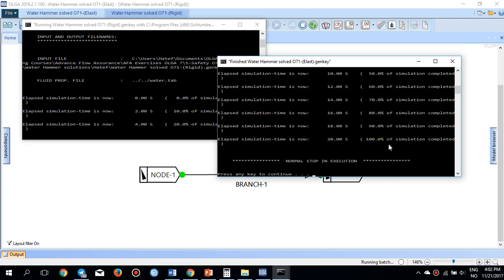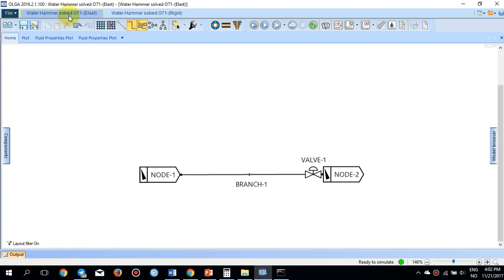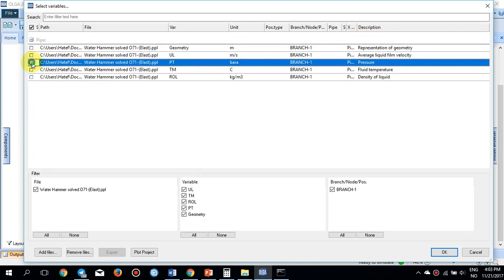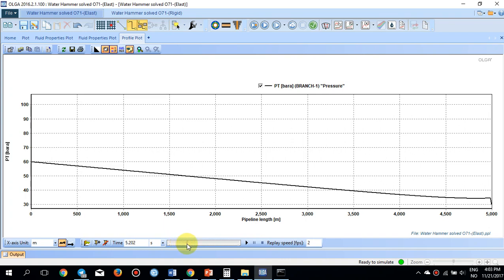The elastic wall simulation has finished. Going to the profile plot and selecting PT — pressure along the whole pipeline — you can see the pressure at the inlet is 60 bar and at the outlet is 30 bar at time zero. As the simulation progresses and the valve starts closing at time T equals 6, you can already see the pressure beginning to build up near the valve.